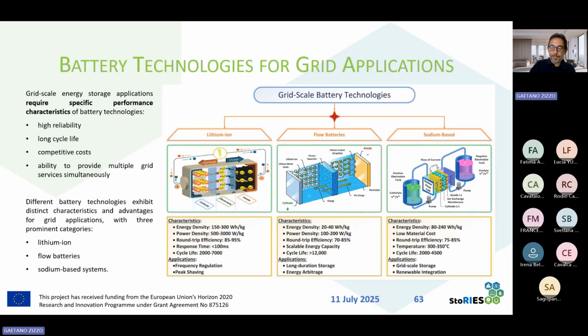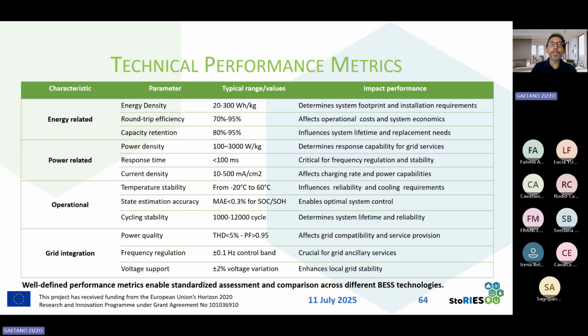Here we compare some performances of the various battery technologies from the tables that I showed you before. You have seen that not all technologies are suitable for providing a given service, so we must compare the different technologies for choosing which one is more suitable for each service, and we can do it based on technical and economical performance metrics. The technical performance metrics are usually these ones. Energy related: energy density, round trip efficiency, and capacity retention. Power related: power density, response time, and current density.